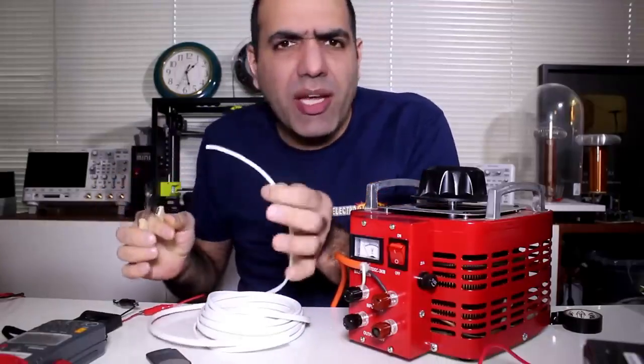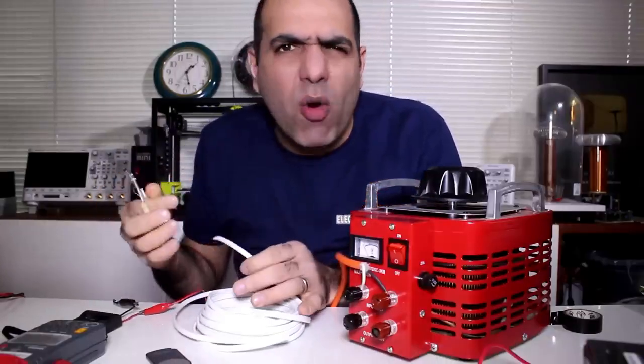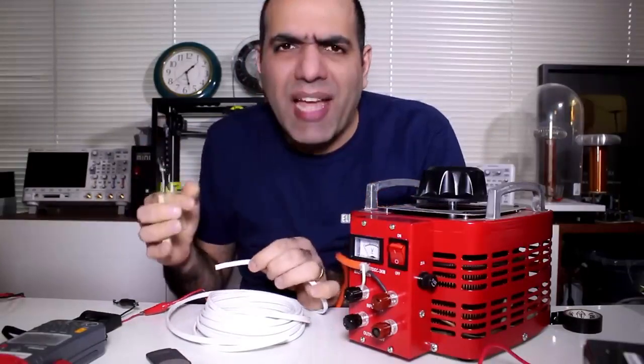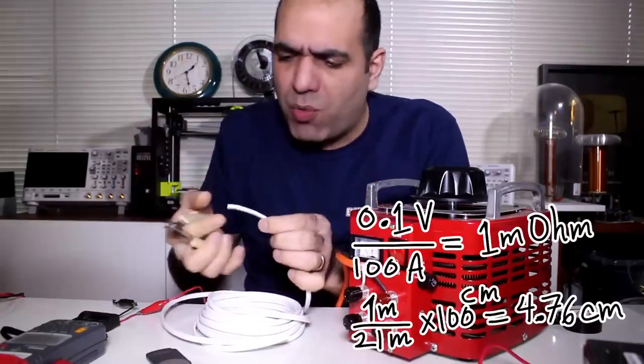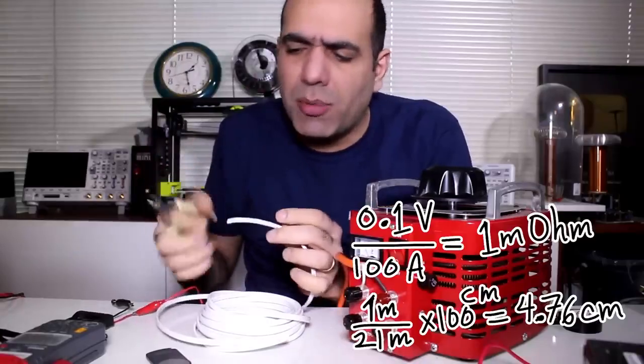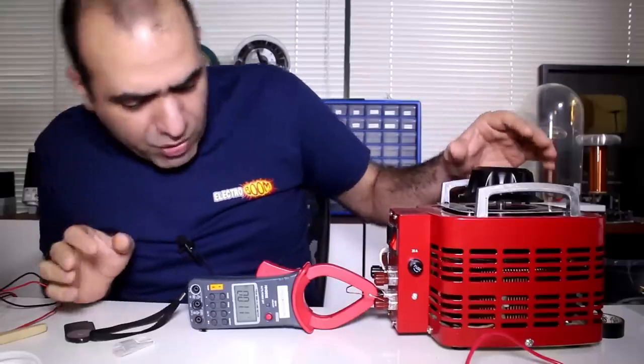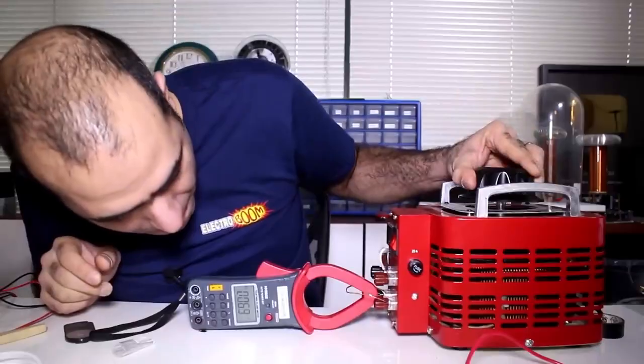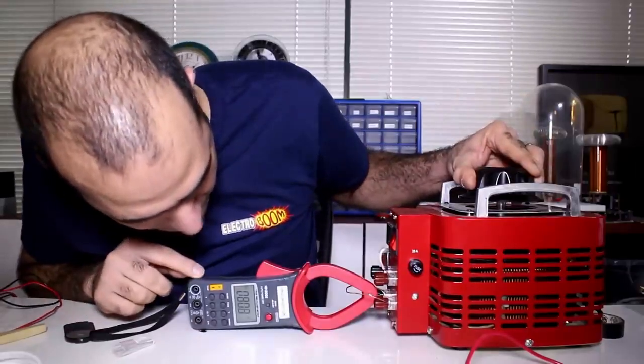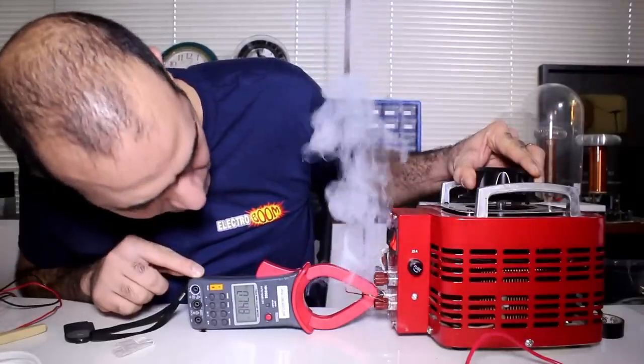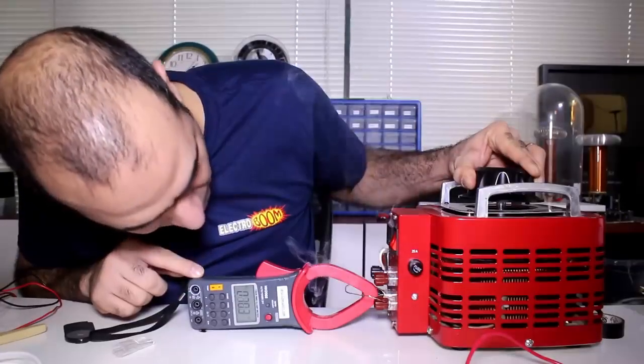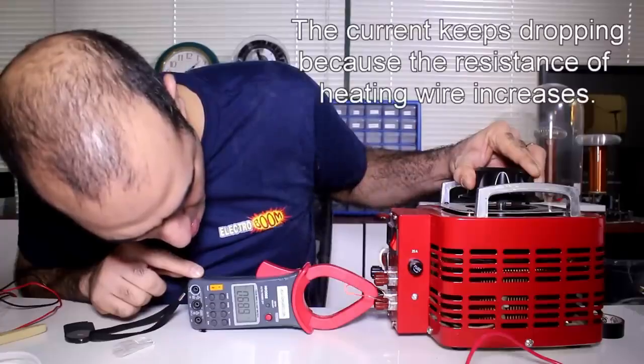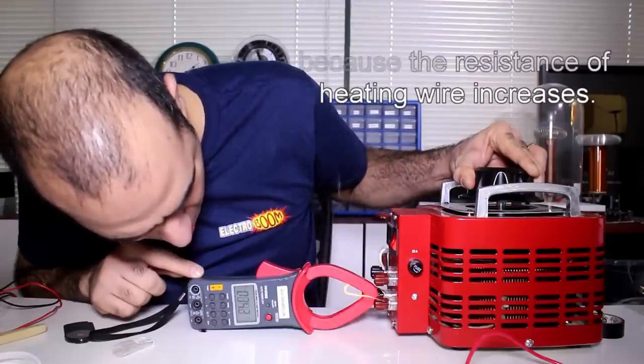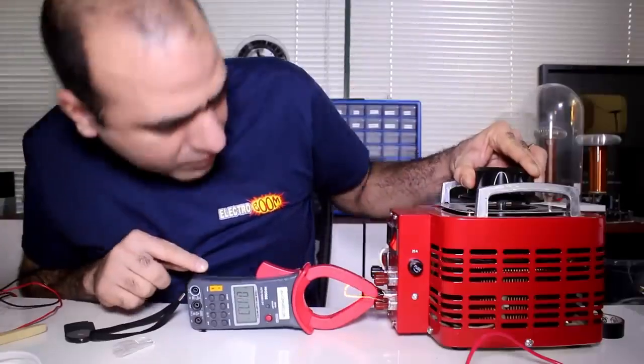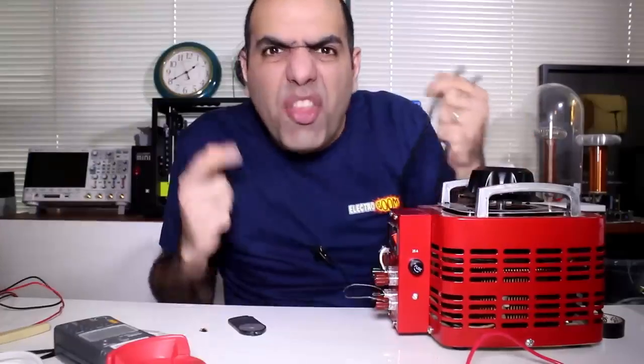I have this 18 gauge wire which is around 21 milliohms per meter. So for 100 amps and 0.1 volt drop, I would need around 4.75 centimeters of this. Okay, let's see if it can do the 100 amp now. There. 77. Ooh, starting to smoke. Come on. 80. Oh, melted again. We need thickness.